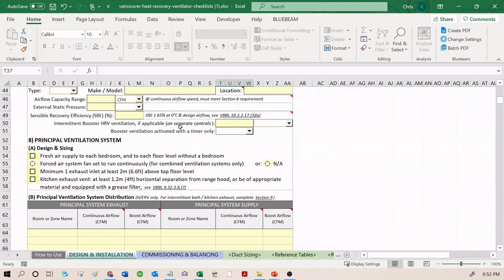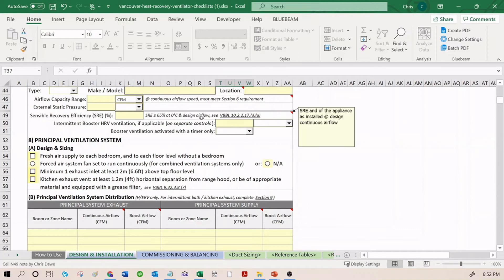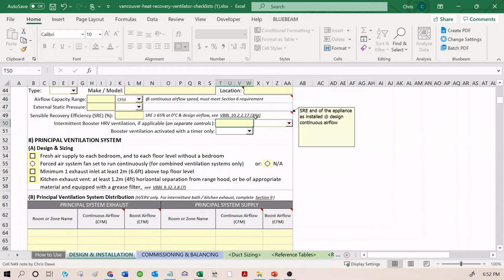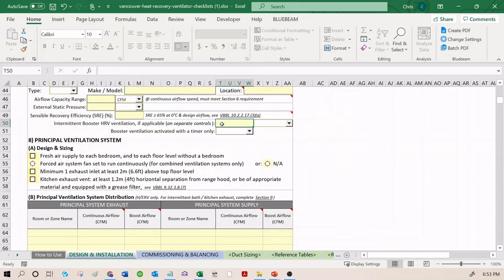One addition on the City of Vancouver checklists is that they're very explanatory about booster ventilation. If you have an HRV configured to run at multiple airflow speeds, depending on if people activate bathroom fans, for example, booster ventilation system is considered and actually written down here. The ventilation ductwork system is sized based on the booster ventilation system flow rate, which makes sense because all the ductwork in the home should be able to carry the maximum airflow rate. So you're going to find lots that refers to booster ventilation.